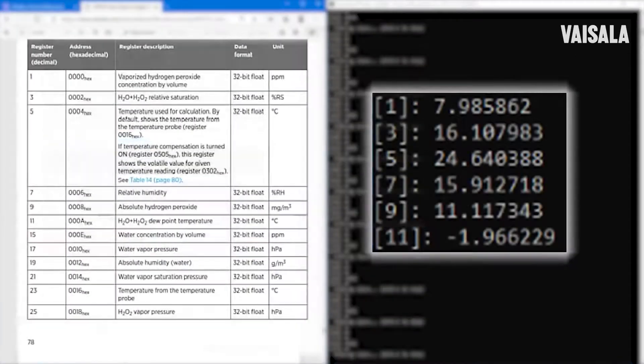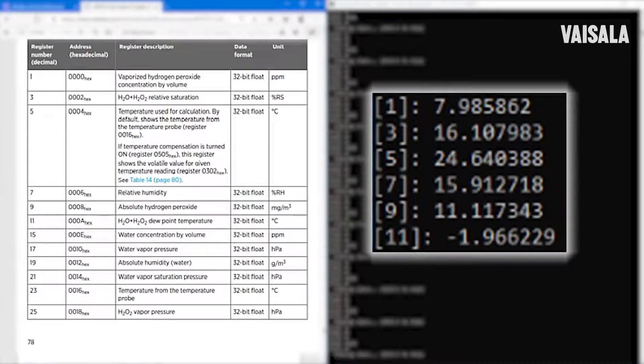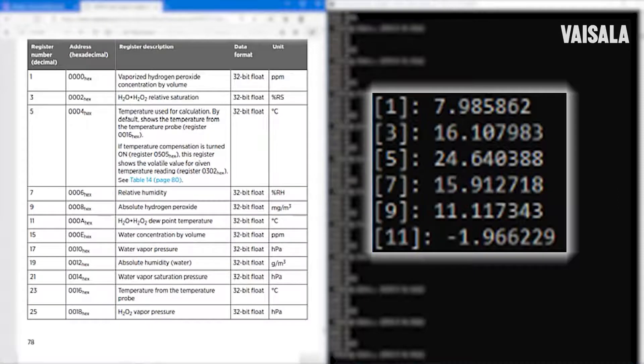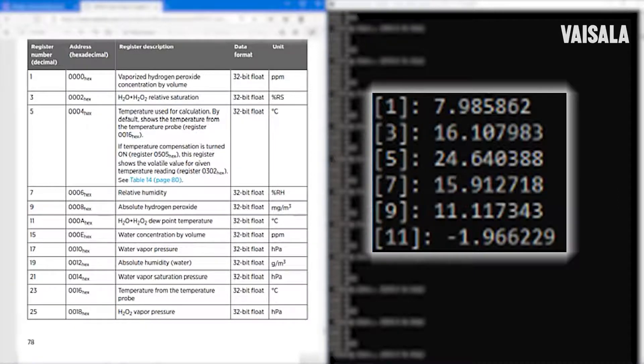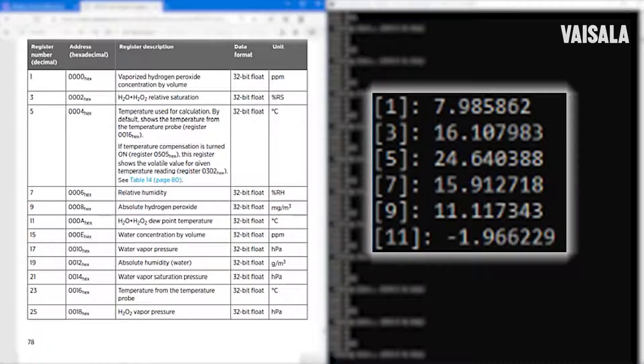The first vaporized hydrogen peroxide is showing now 8 ppm, and relative saturation is 16. Temperature is 24, and relative humidity is quite the same as relative saturation. And then there's also absolute hydrogen peroxide value and mixture dew point temperature. And these are very useful parameters for some applications.